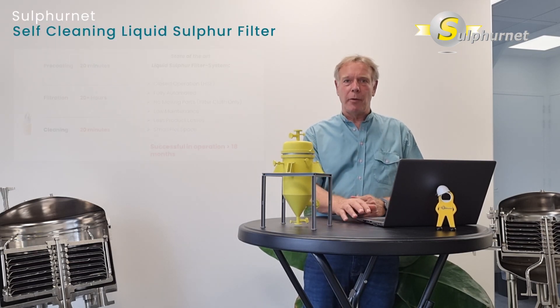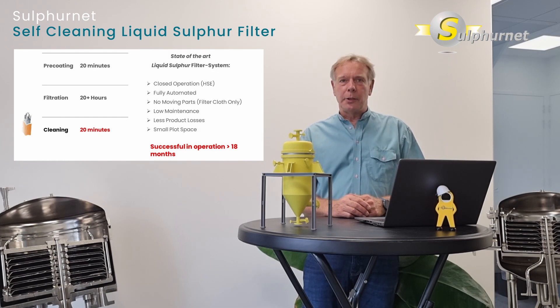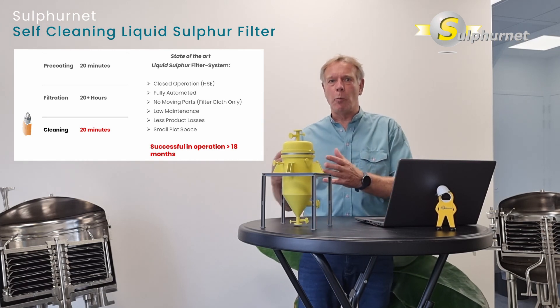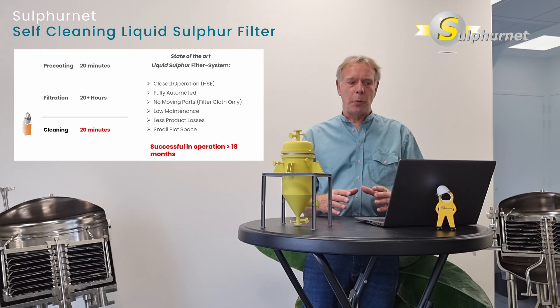At Sulphurnet, we have developed a new self-cleaning liquid sulfur filter. The filter operates similar to a pressure leaf filter. We have a pre-coating time of 20 minutes, a filtration time of 20 hours or more depending on the solid load in your system, and a cleaning time of only 20 minutes.